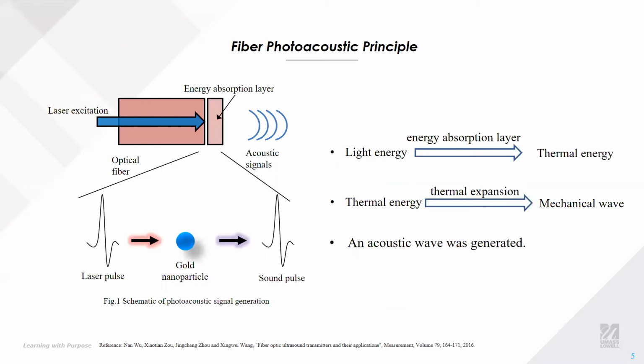So how do we generate the ultrasound from optical fiber? Maybe the previous presenter has talked about that. Basically, the energy from the laser will be absorbed by the photoacoustic generation material on the tip of the fiber, and that material will absorb optical energy and convert it into thermal energy, and then the material will expand. And because we use a pulse laser, when the laser is off, the material will contract. Expansion and contraction then generate a mechanical wave. So this is how we generate this acoustic signal from the optical energy.